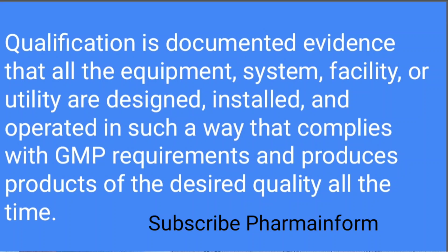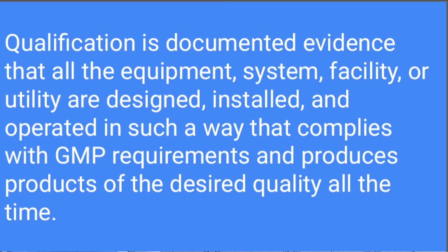The next question is, define qualification and its components. Qualification is defined as a documented evidence that all the equipment, system, facility or utility are designed, installed and operated in such a way that complies with GMP requirements and produces products of the desired quality all the time. What are the components of qualification? Components of qualification are URS, user requirement specifications, FAT, factory acceptance test, SAT, site acceptance test, then DQ, design qualification, IQ, installation qualification, OQ, operational qualification, and PQ, performance qualification.